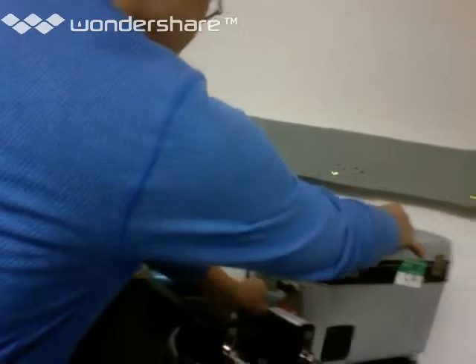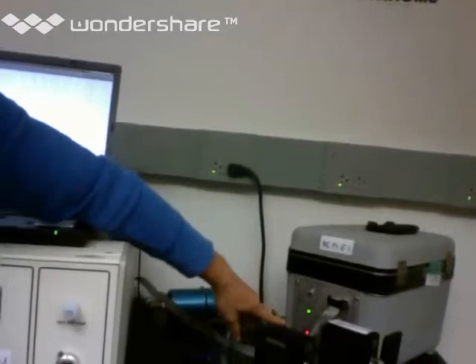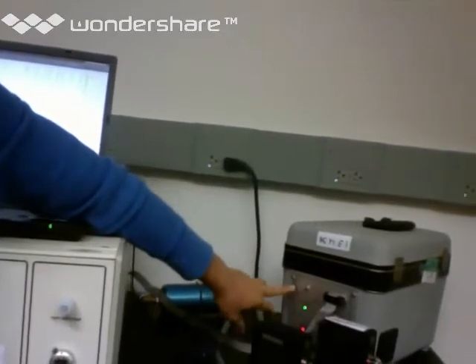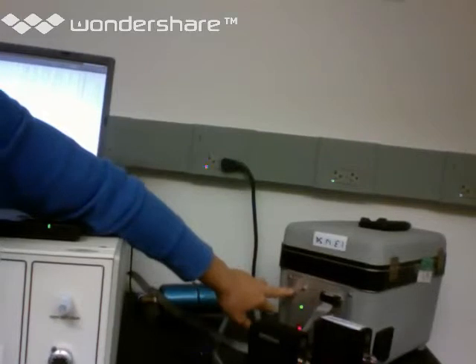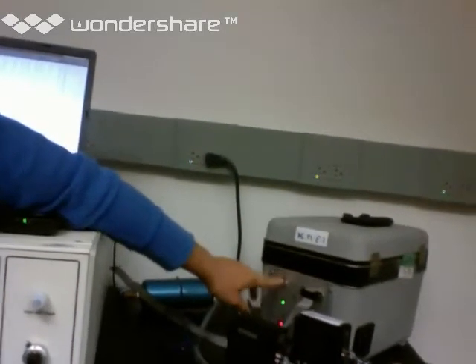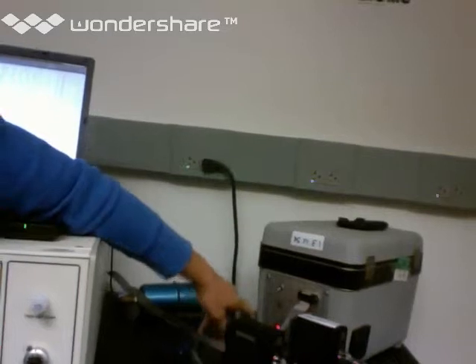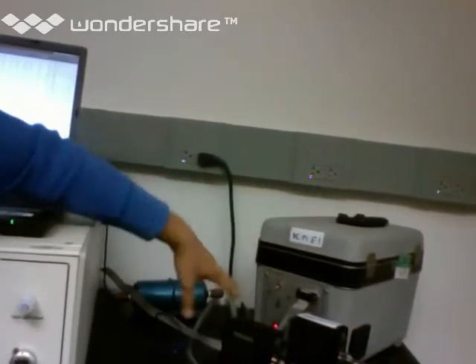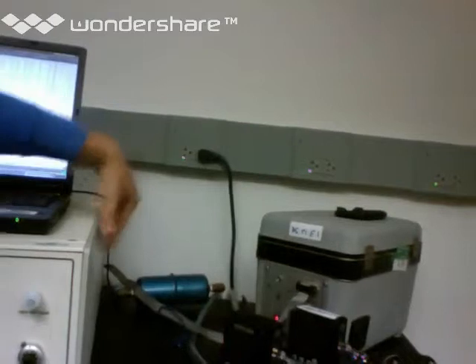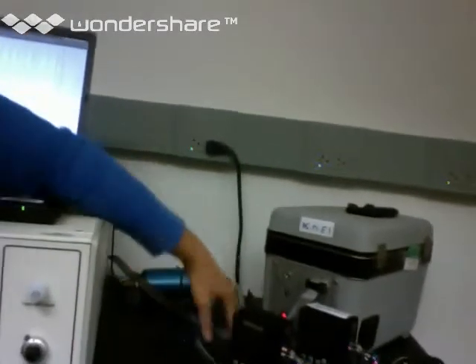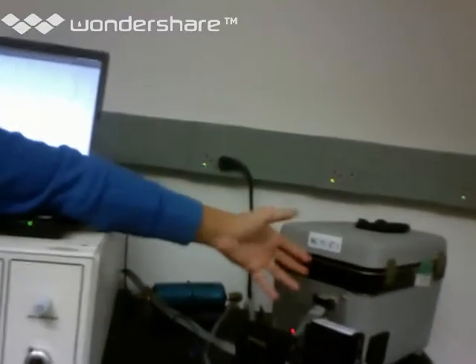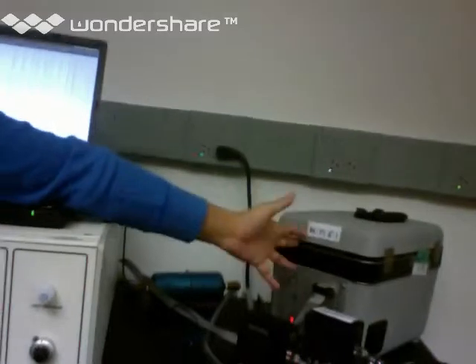So if you look at the, I can shift this around to show you. So if you look at the panel of the zero air, it's got the information input port, it's got a power cord, and it's got a power switch, as well as a mode. It's got an on, off, and an auto mode. Typically, you can just leave this in auto, which I'm going to do right now. If it's in auto mode, it's basically slaved to the Tekran. When the Tekran sends out a message on the ribbon cable for this to start, it'll start. If it doesn't, it won't. It's a conservation measure. It won't eat up energy.